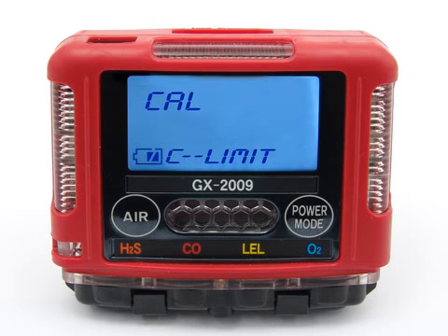If Cal Limit display function is turned on, the screen that appears next depends on how Cal Limit check is set. If the unit is due for calibration and the Cal Limit check is set for confirmed to use, then the Cal Limit prompt will display and the alarm LEDs and buzzer will pulse several times. When this occurs, press and release the power mode button. You will hear a beep and the startup sequence will continue.